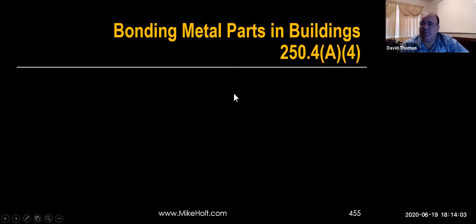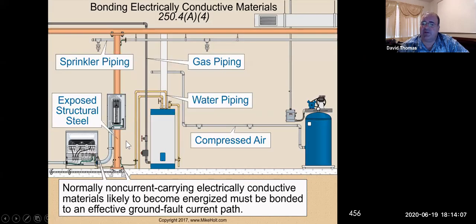Bonding metal parts in buildings. 250.4(A)(4) says that we have to bond any parts in a building that are metal, which means that if I have sprinkler pipe, I may have to ground it, or if I have a gas pipe, I may have to ground it.